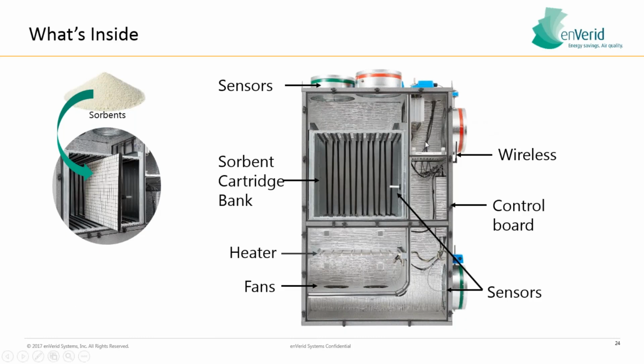We draw air into the unit past this little pre-filter here. There's two little 120 watt muffin fans here at the bottom to help overcome the unit's own internal static pressure. That air flows over these cartridges and then back into the return air. We have a controls board to interact with the building's management system, the BMS. We also have a wireless card to transmit air quality data and modeled energy savings, as well as unit status and operation to the enVerid cloud.